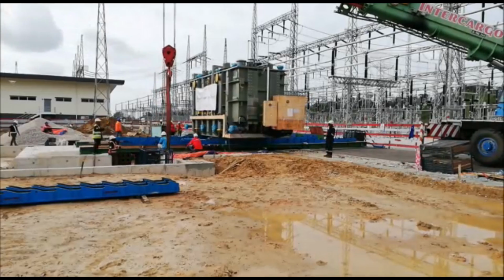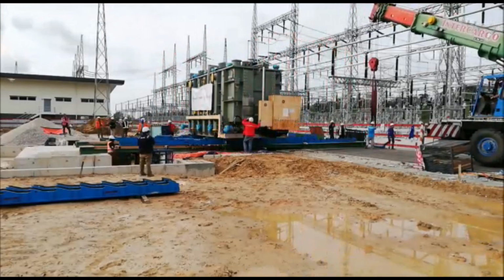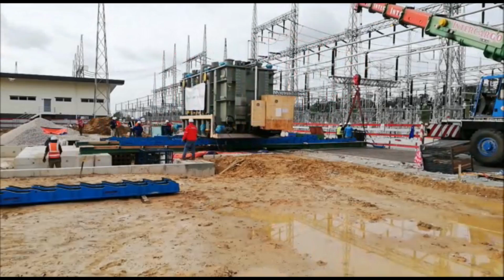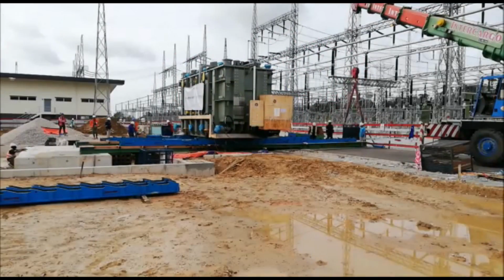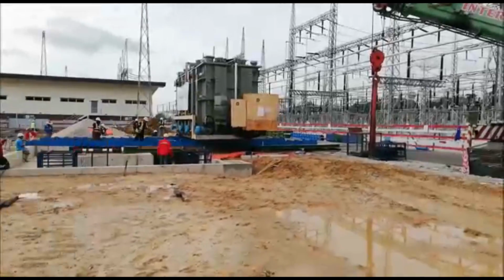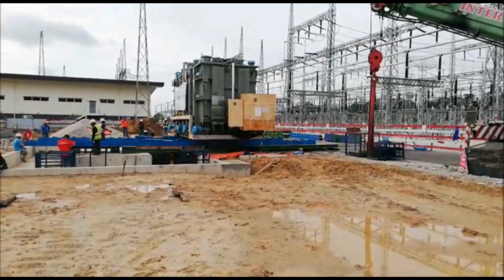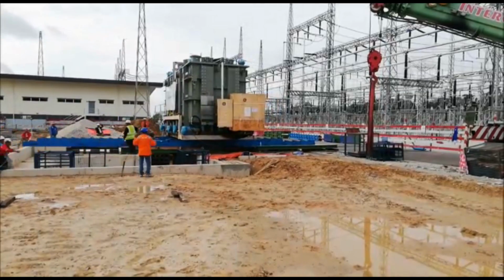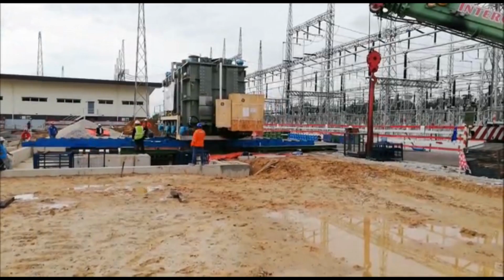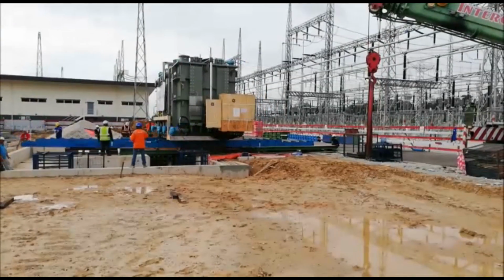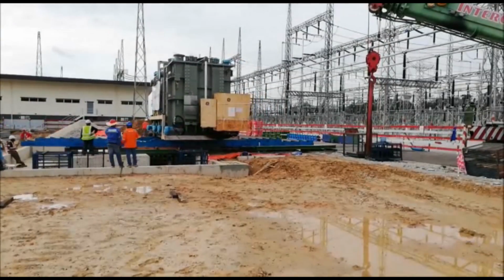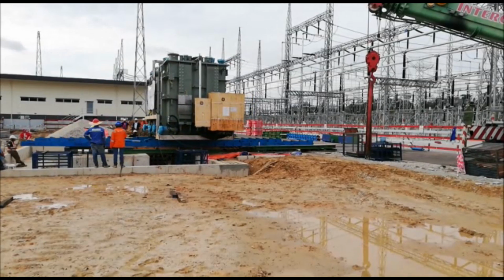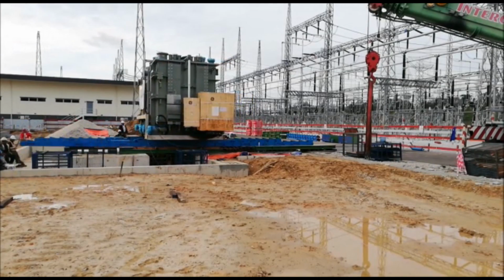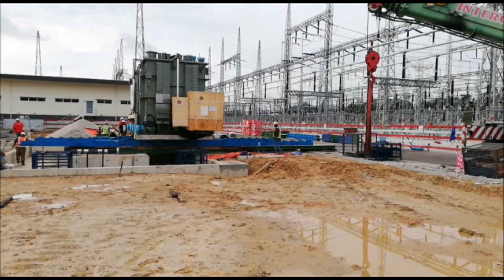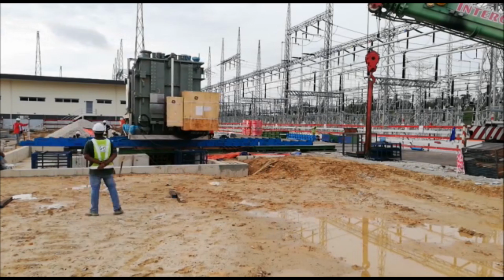7. Jack down the transformer over the transformer plinth. This has been the fastest and most effective skidding and jacking method executed in this region. It took only 2 hours to position the transformer from the road to the plinth, covering a distance of about 15 meters — a critical task safely achieved the L&T way.